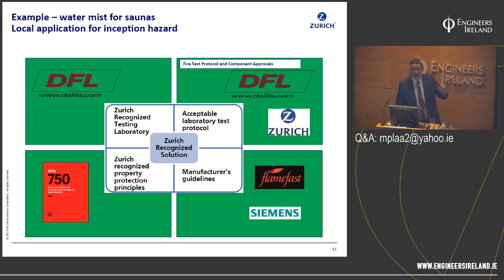So we have the Danish Fire Labs. So we have an independent accredited third-party test. We have a global standard linked to also the CEN standard. We have fire test protocol from the Danish Fire Lab and component standards. And we also have the manufacturer's instruction. So having gone through that rigorous 4-stage process, I can be confident that that system is fit for purpose. The evidence has been provided, and also I need to back that up by an on-site test as well to make sure they will actually work in anger.